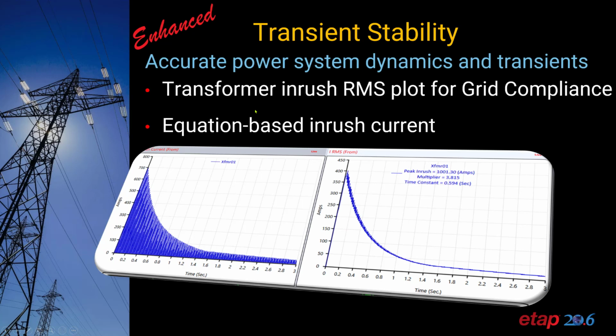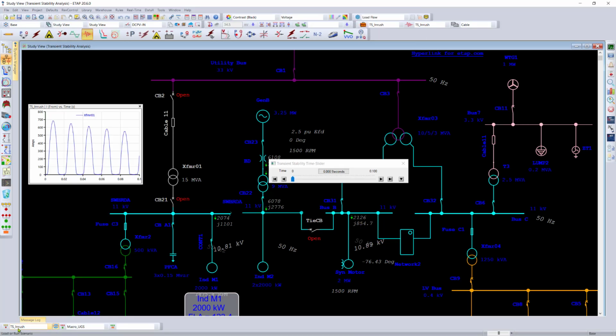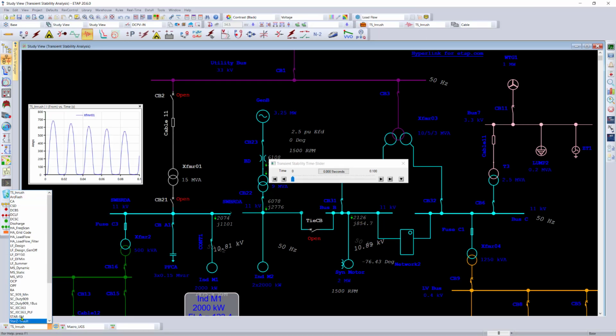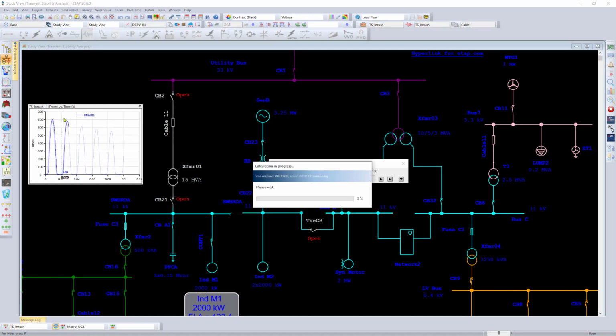ETAP transient stability has been enhanced to include transformer inrush plots for grid compliance and includes a new equation-based inrush current capability. So let's go ahead and see both of these two in action. We can simply go into our transient stability scenario and run this scenario for us to visualize what happens when we run the actual calculation.